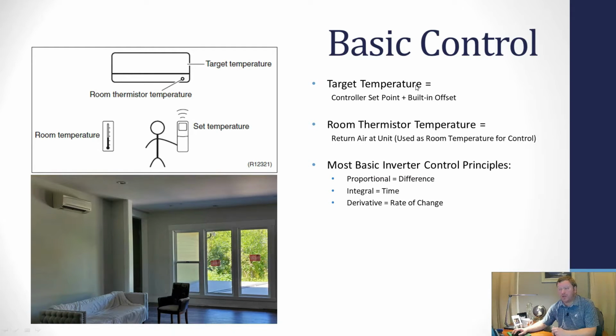So your target temperature is what the system uses for its control algorithm, and we'll talk about that algorithm in just a second. It's not the actual set point that you give the unit on the handheld remote controller though. You have to remember there's an offset because the unit is mounted up by the ceiling. So I give my unit a set point of 70. It calculates the offset and says, okay, internally I'm going to try and maintain a return air temperature of 73.5. That's that target temperature. So now what happens is something called PID logic.